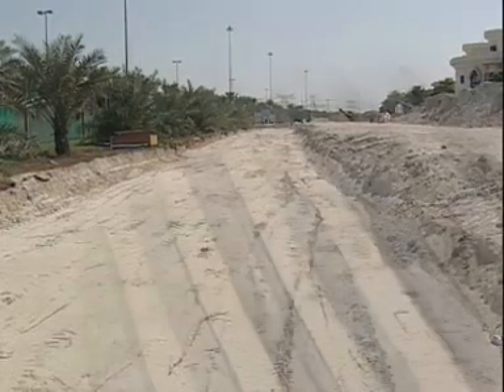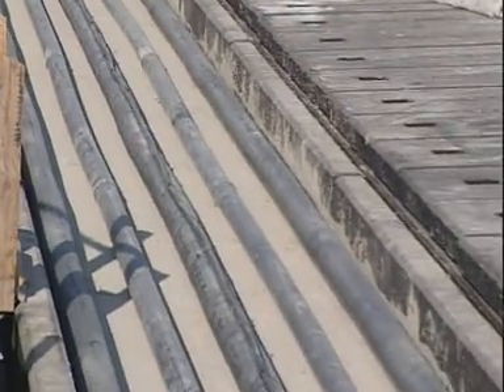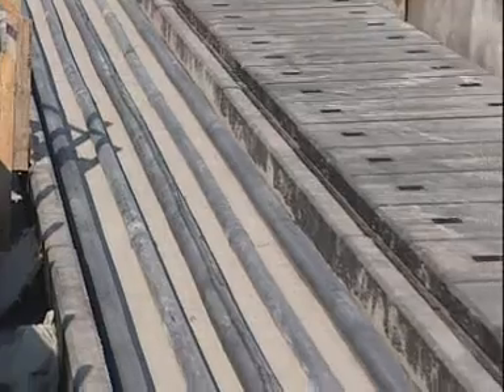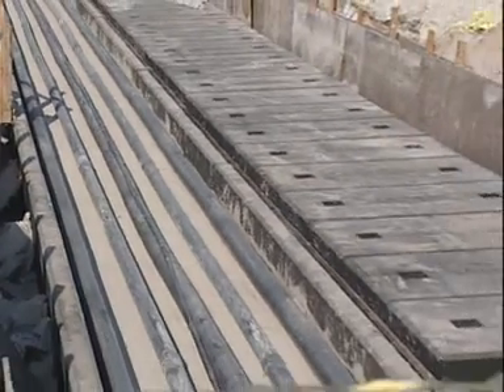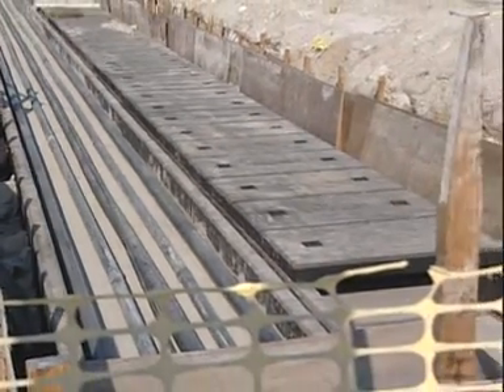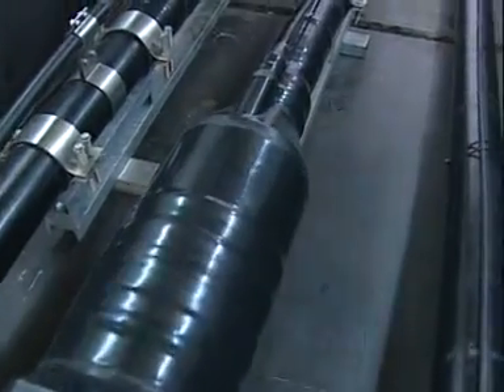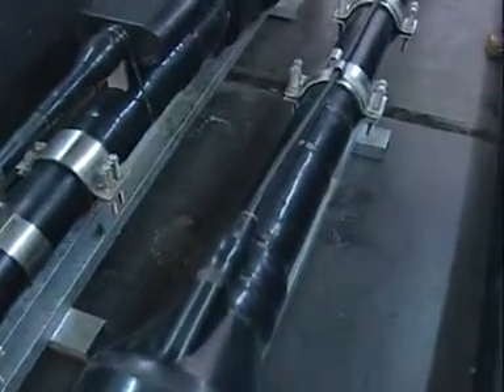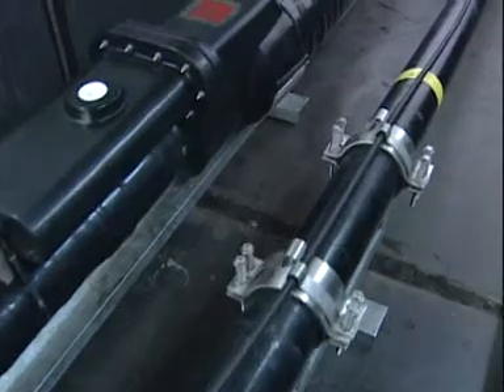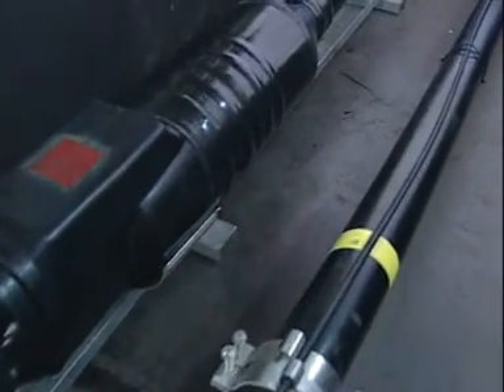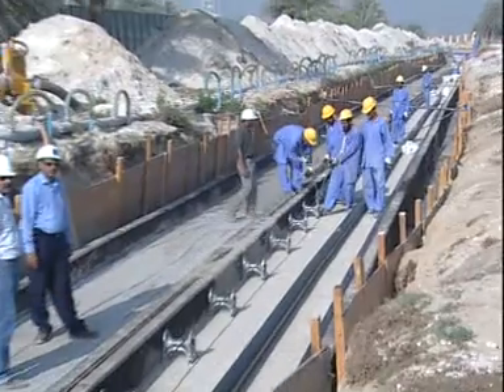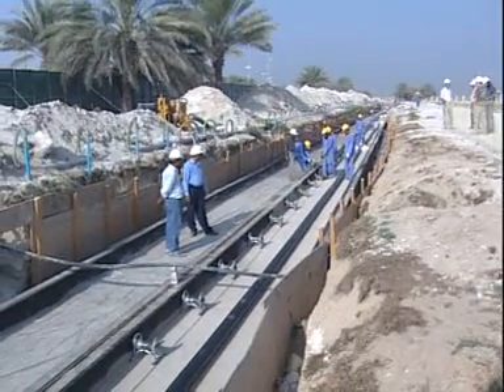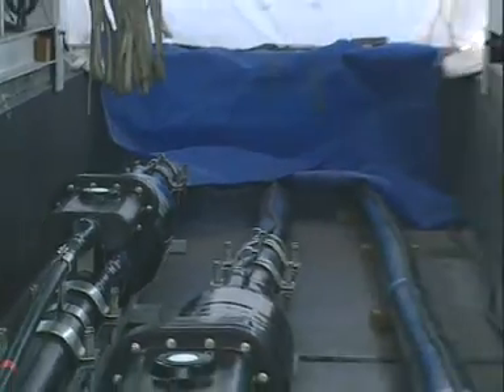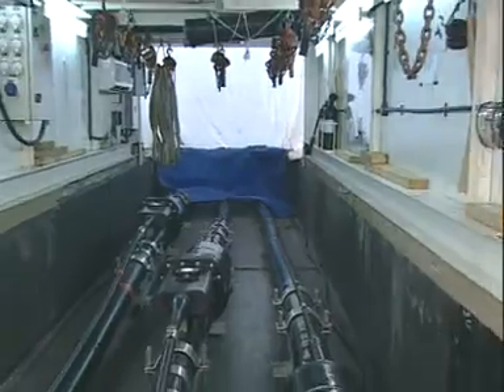In parallel, a fiber optic cable is drawn on one of the faces and connected to a measuring instrument known as a DTS transducer. This device measures the temperature along the whole length of the cable, thus ensuring optimum energy supply with no risk of overheating, even locally. The cable is laid in 480-meter lengths. Its metal screen is connected to the ground by a cross-bonding system.